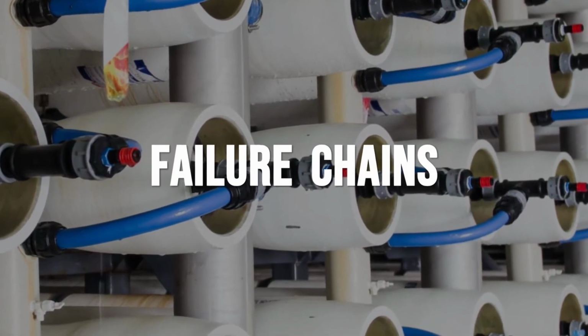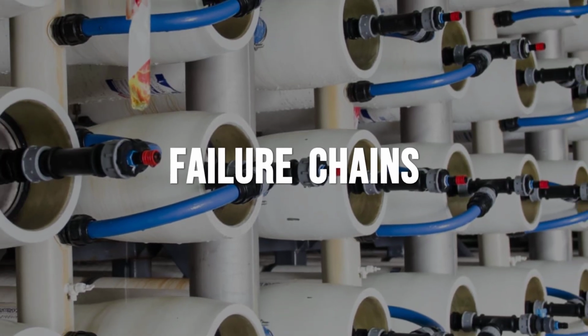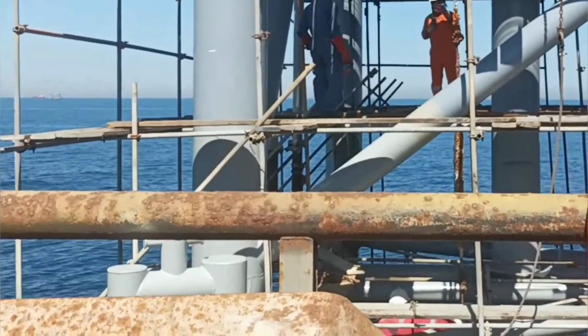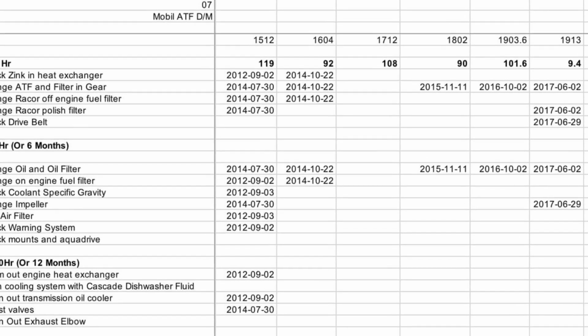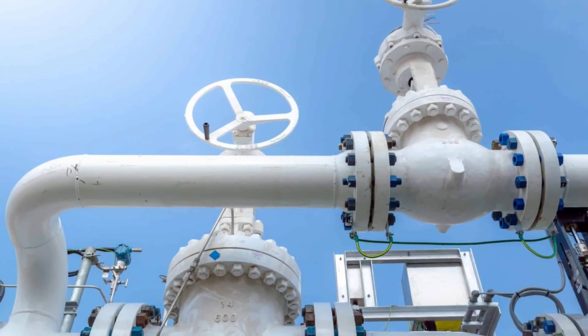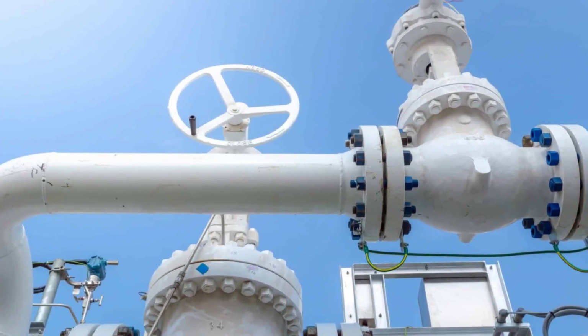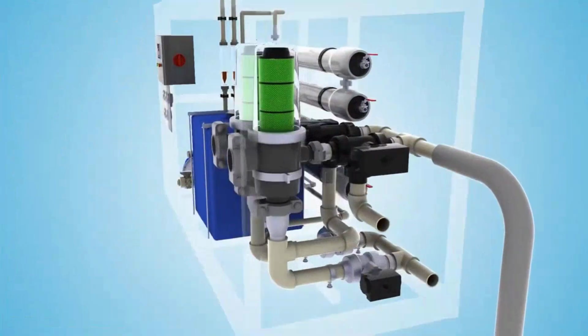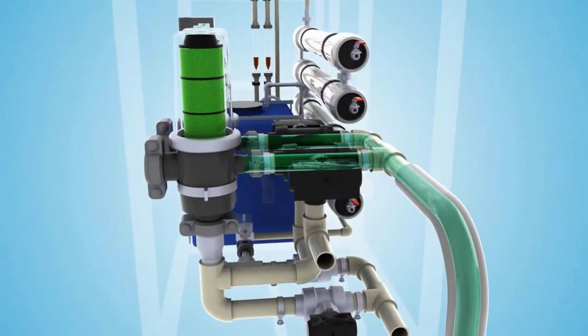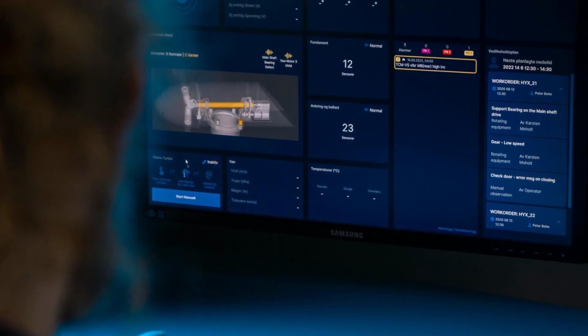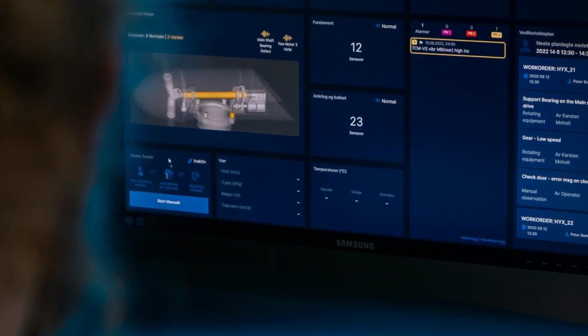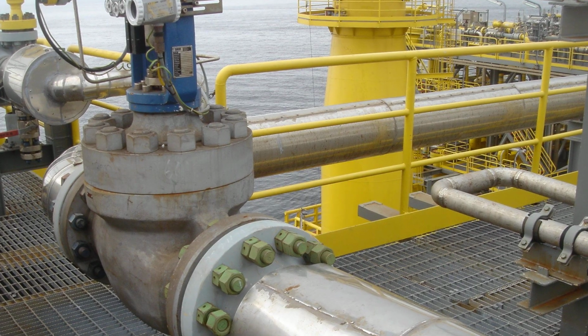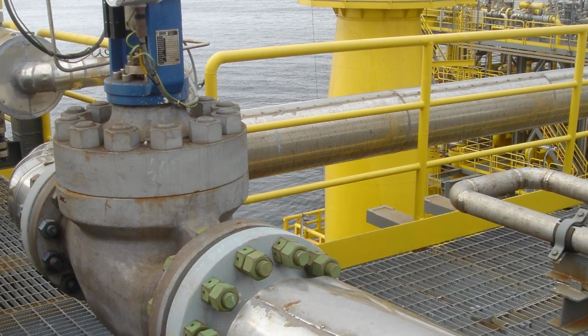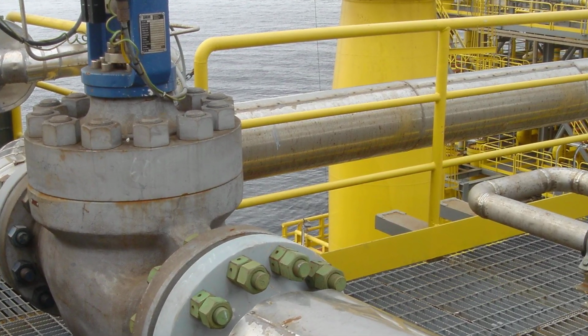At 8 in the morning on day 0, a seawater strainer in the desalination loop showed rising differential pressure after a week of heavy silt in the intake. Maintenance flagged it for cleaning, but with production targets looming, the job was deferred to day 2. The decision was logged, the bypass noted as temporary. By midday on day 1, the main desalination train tripped on low flow. Salinity alarms lit the SCADA screens, and the standby unit failed to start because an isolation valve, left closed from a prior bypass, blocked the transfer.